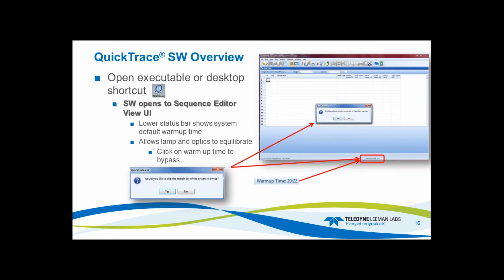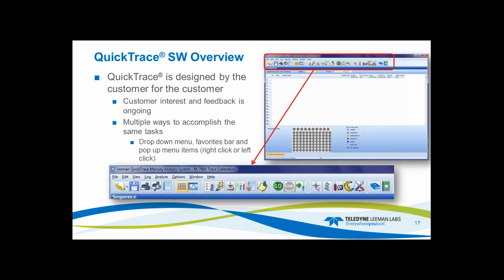So we use QuickTrace software, and you open the executable or the shortcut on the desktop. The software opens the sequence editor view UI. The lower status bar on that user interface has a warm-up time, and that allows the lamp and the optics to equilibrate. You can click out of this if you want to, bypass it, and move right into the software. So this software is designed by the customer for the customer.